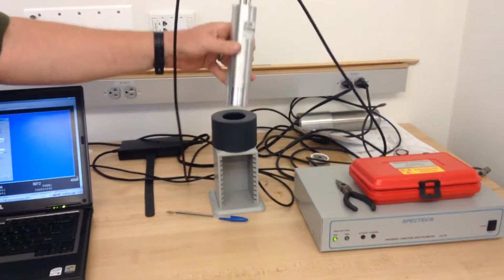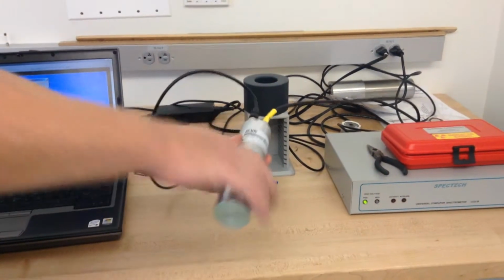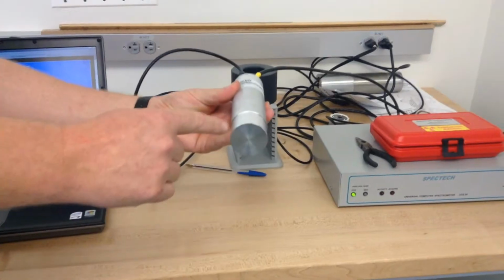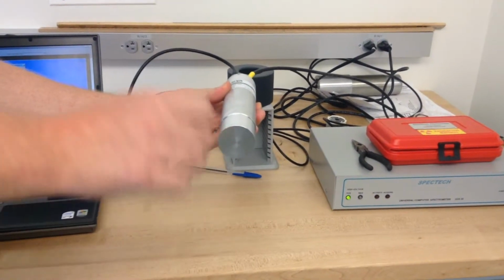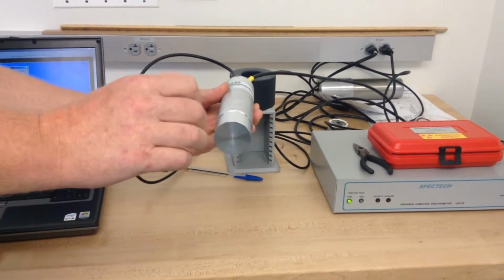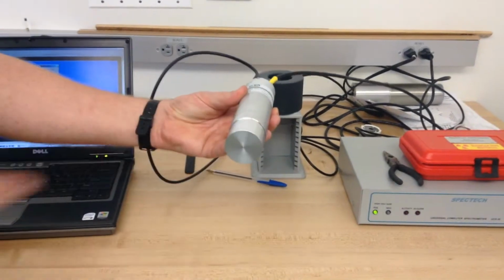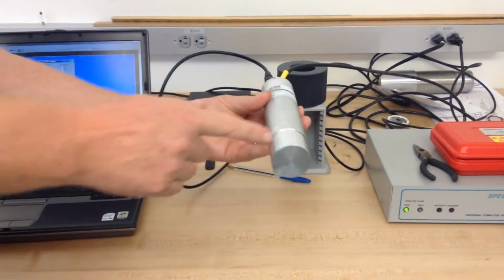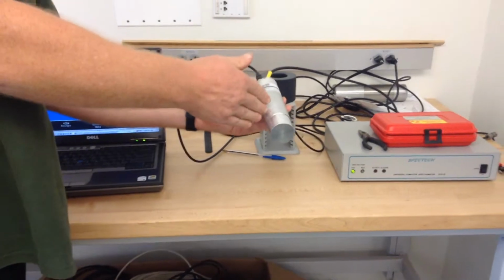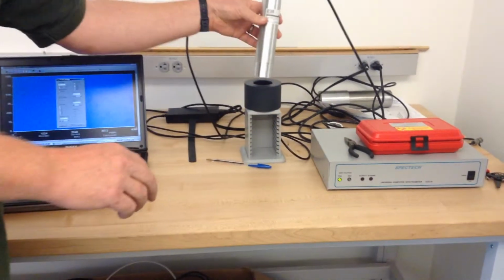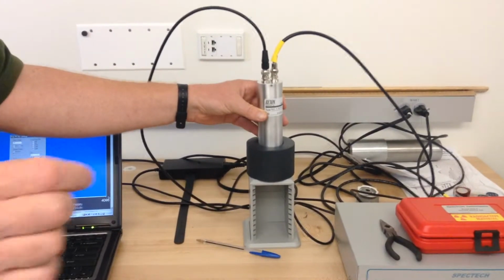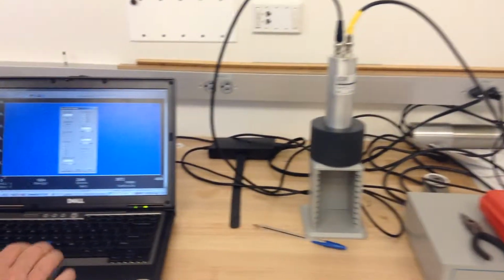This is a sodium iodide detector. We need to put 740 volts across some electronics down here. There's a crystal here. When a gamma ray comes in, it scintillates. That means it sends out visible light. As the gamma ray goes through, it just leaves a streak of visible light. That visible light is picked up in photomultiplier tubes, and that's the thing that needs 740 volts to amplify a current from a given dumping of energy.